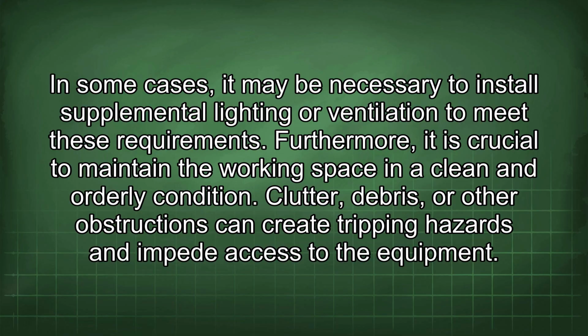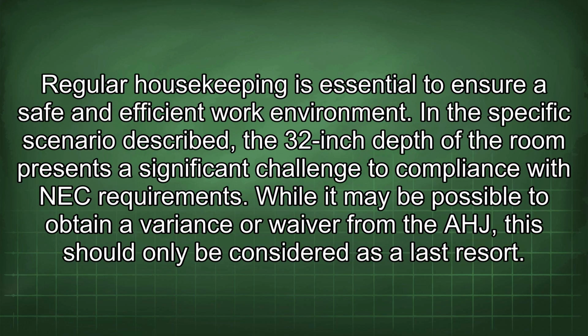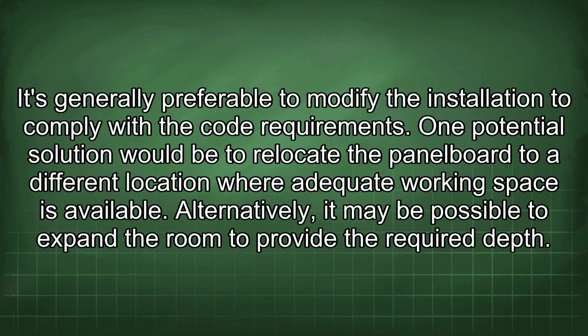Furthermore, it is crucial to maintain the working space in a clean and orderly condition. Clutter, debris, or other obstructions can create tripping hazards and impede access to the equipment. Regular housekeeping is essential to ensure a safe and efficient work environment. In the specific scenario described, the 32-inch depth of the room presents a significant challenge to compliance with NEC requirements. While it may be possible to obtain a variance or waiver from the AHJ, this should only be considered as a last resort. It's generally preferable to modify the installation to comply with the code requirements.